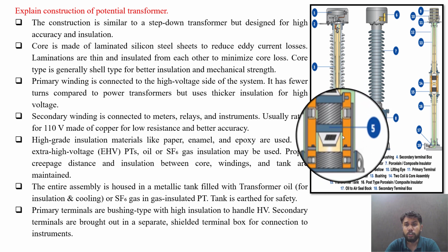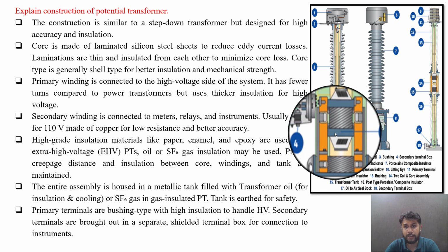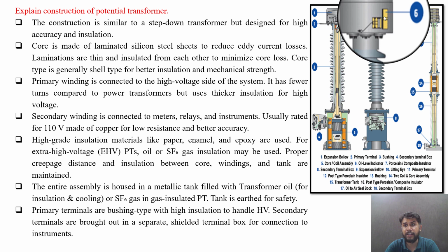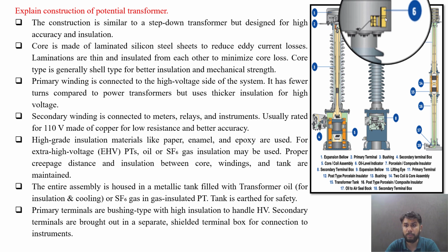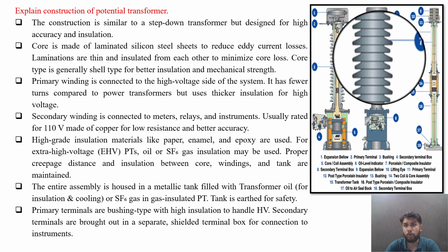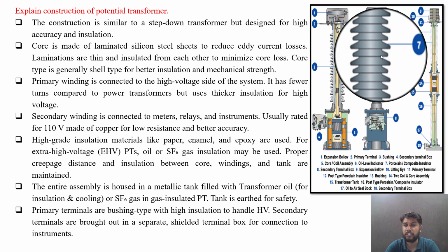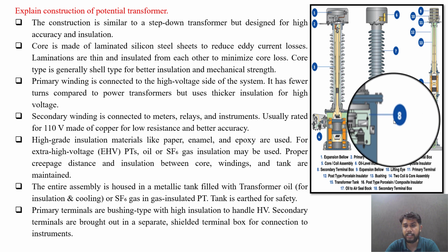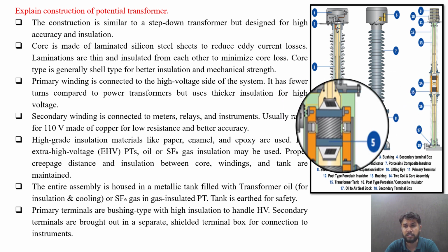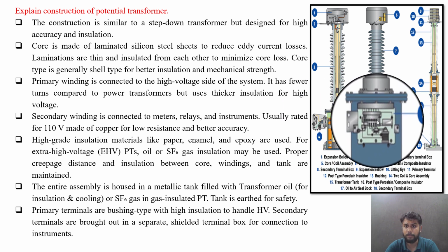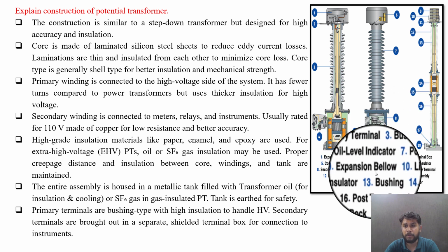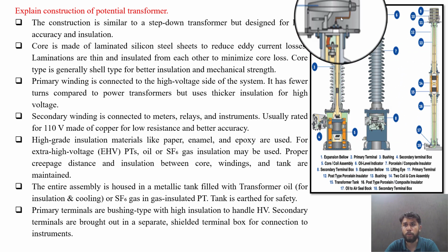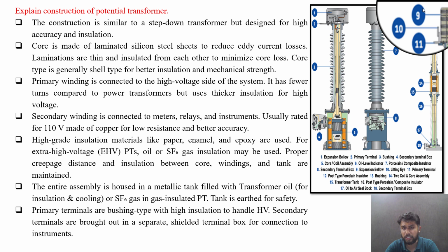5 is the core or core assembly here. 6 is the oil level indicator at the top of the PT. 7 is the porcelain insulator or composite insulator covering on the outer surface. 8 is the secondary terminal box that is shown in this. The front view is here. 9 is the expansion bellow which is at the top of this. This one number is the same.